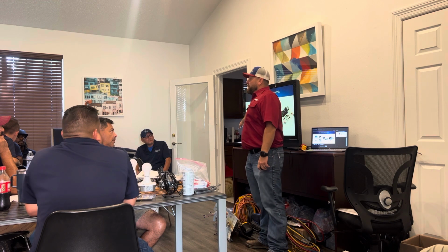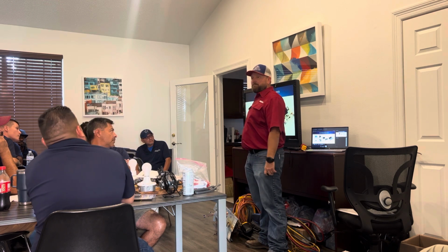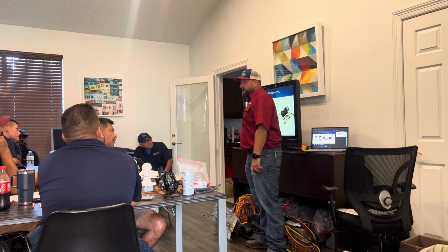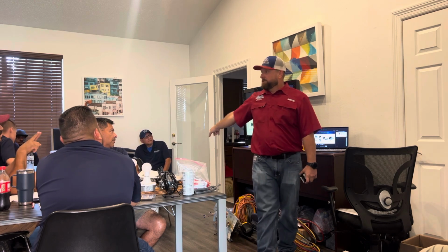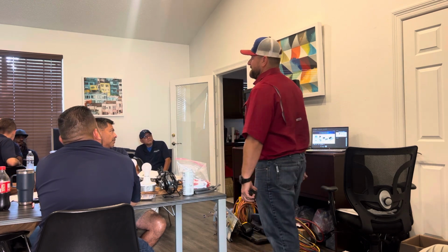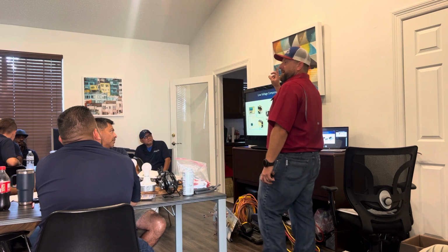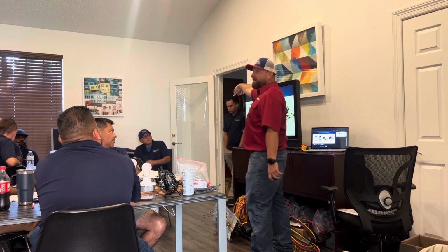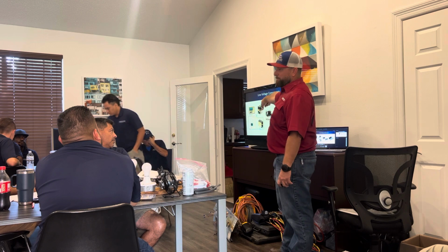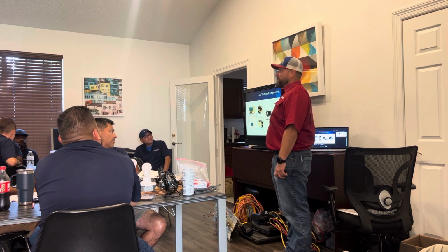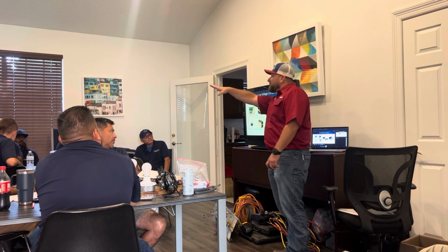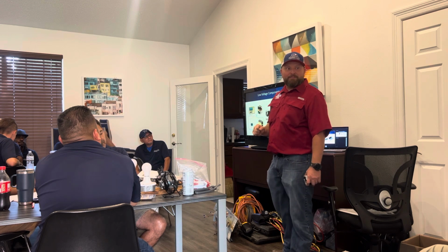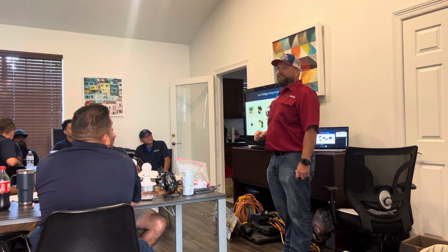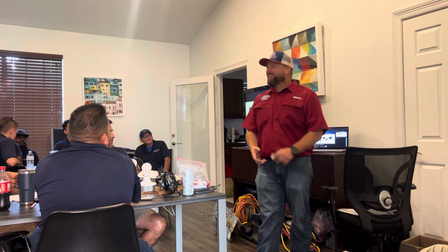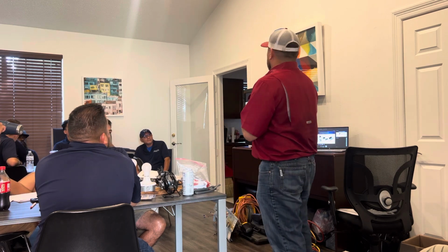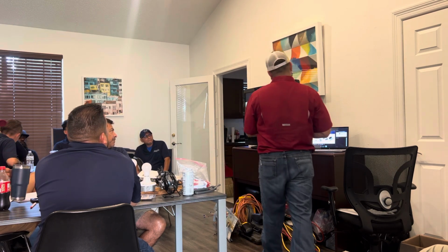A quick side note: if you ever change a transformer, always put an inline fuse on the red side. That will save it - if you've got a bad thermostat and it's grounded, it'll pop that fuse instead of your transformer. I'm sure some of y'all have had a transformer blow up in your face - it's not fun. We got one back here that did it. So these fuses are really where it's at.